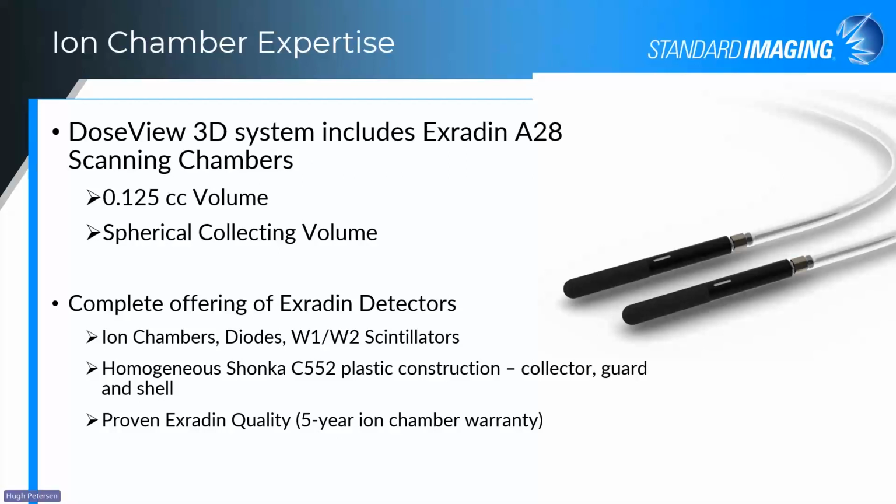very strong chamber. They don't wear out, they don't really degrade over time or get brittle like a graphite chamber does. And because of that, we offer a 5-year warranty, which is unheard of in the industry. Nobody else offers that kind of warranty on their ion chambers. And another point, we also have an extended warranty available to extend that out to 10 years for a very reasonable cost as well.